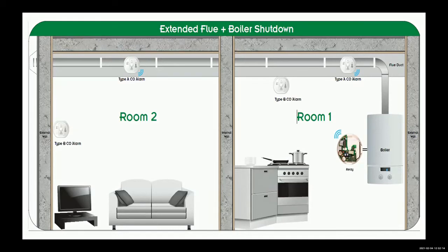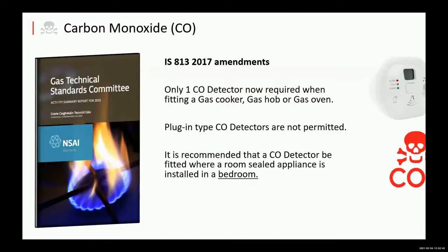Within each room that the duct or void passes through, you have to put a Type B device. And the Type B device is defined as a carbon monoxide alarm. It detects carbon monoxide, it sounds, and that's it. It doesn't do anything else. It's a standalone unit. And if you look at the room where the appliance is, on the right-hand side, it's on the ceiling. And if you look at the room on the left, room 2, it's on the wall at breathing level. And we'll go through the location of the devices in a second.